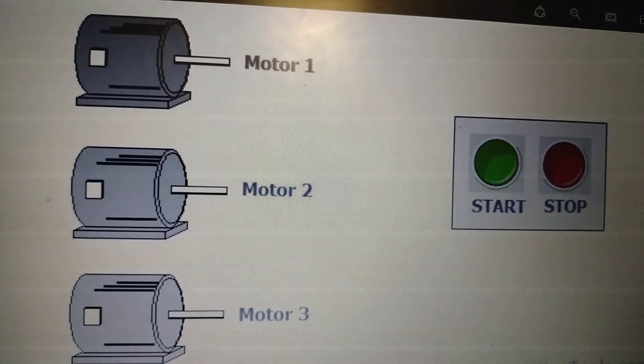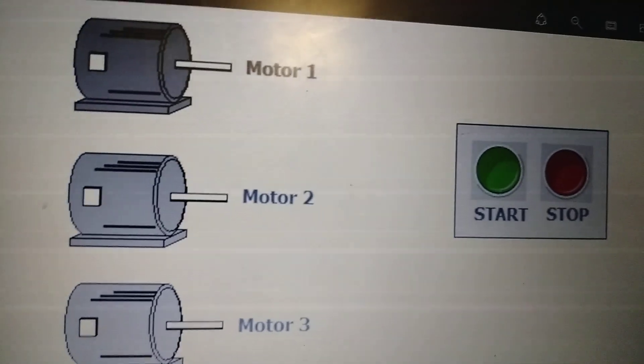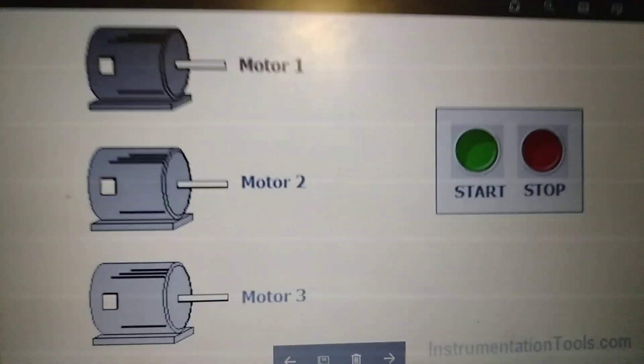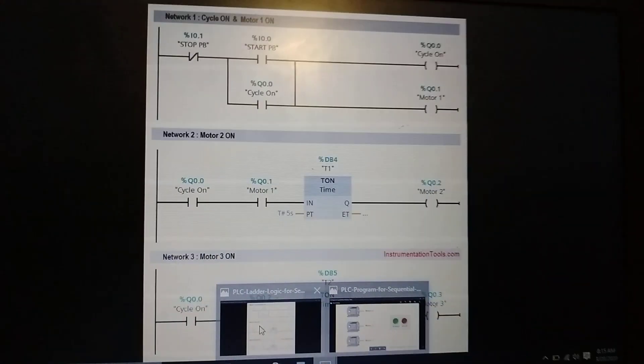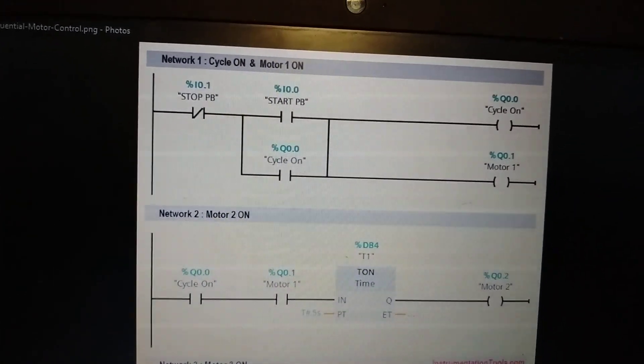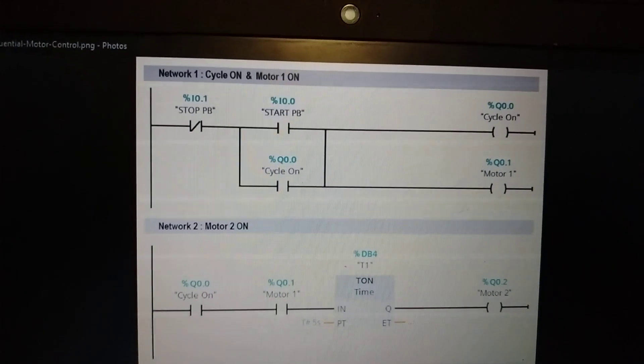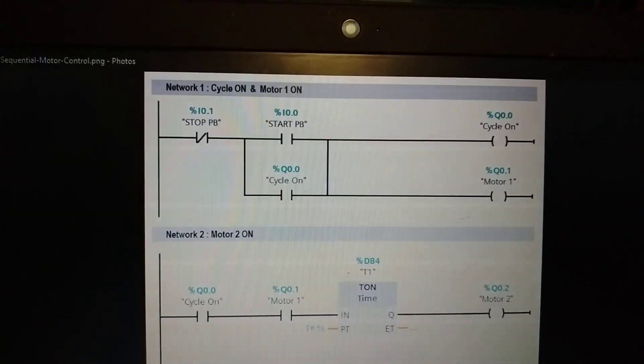During initial startup, a five-second time delay is provided between operations of each motor. We have two input states and four output states. The two inputs are the start push button and the stop push button. The four output states are cycle on, motor one, motor two, and motor three.